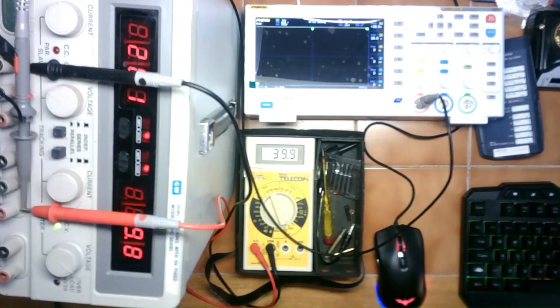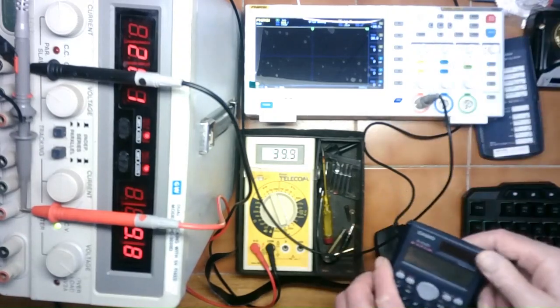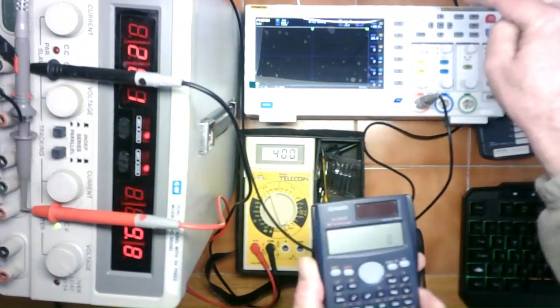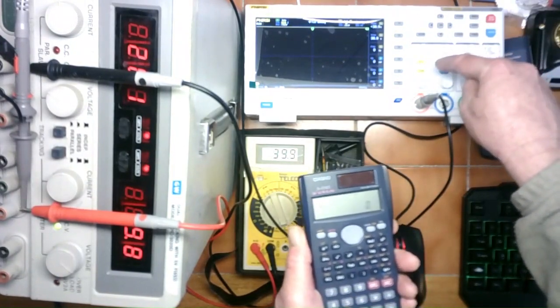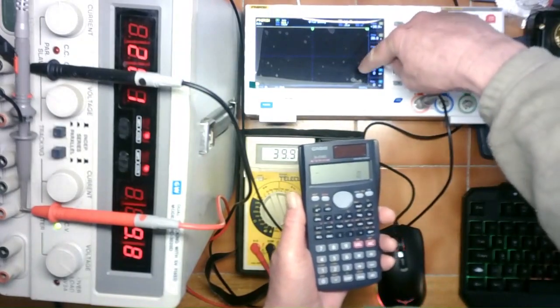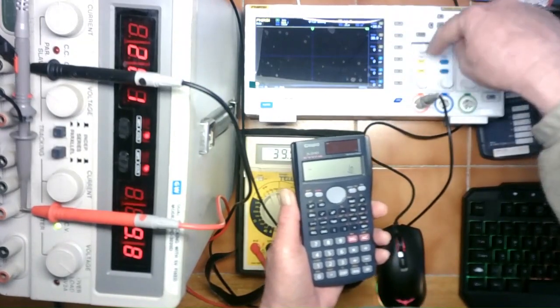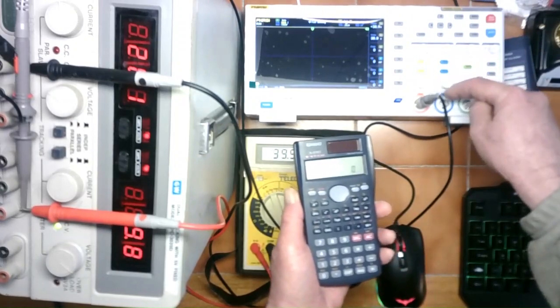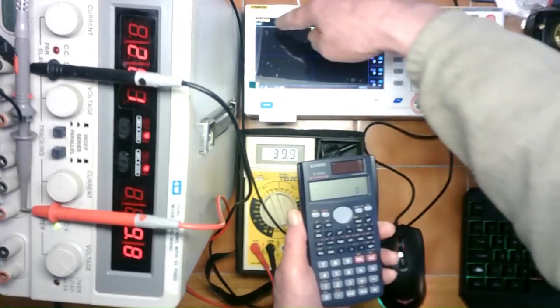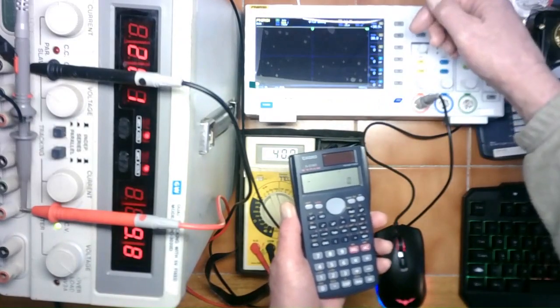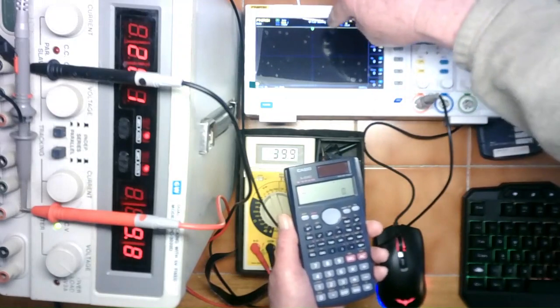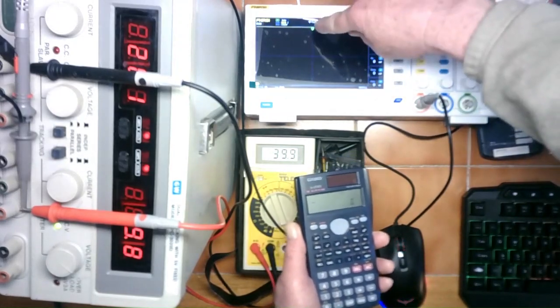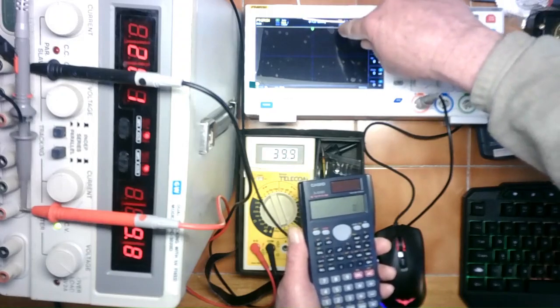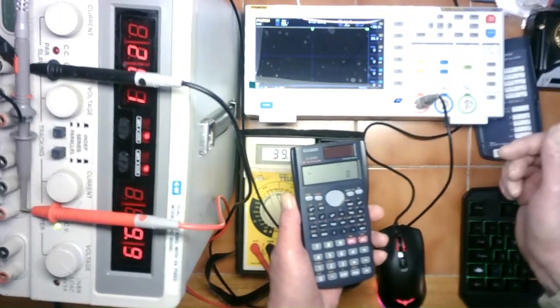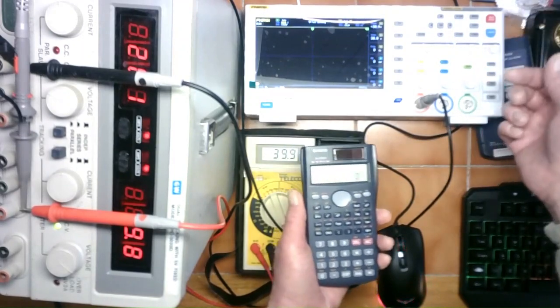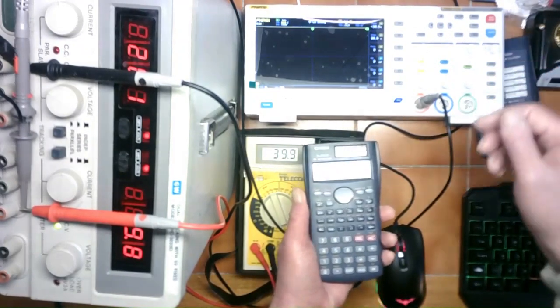So already you can see the inaccuracies of the unit, and this has now had the version 3 firmware upgrade done to it. What it should be reading is 40 volts here, because that's its actual specification for its maximum input before the signal goes off the screen, which means in this case the line just hits the top and won't go any further. With an AC wave, it means that it peaks out on the screen as well, and you get the top chopped off. If you had a wave going across the top, that gets cut, which is what we saw in that Murphy video when I was measuring the diodes and the mains input transformer.